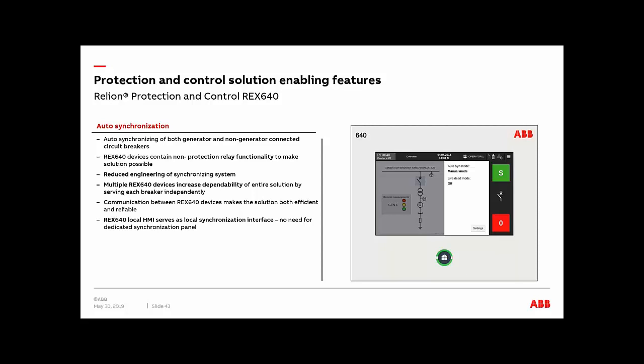And you can have multiple, actually in this scheme, you need to have multiple REX640. The system has to be comprised of 640 relays completely, so you can implement a successful auto-synchronizing scheme of, remember, up to 8 generators and 17 non-generator breakers. And as far as you having a dedicated panel for synchronization, each of the relays will have the information that you need with the synchroscope and all the information as far as the synchronization. So you can do it locally on the relay, or you could do it in the web browser as well, which will show you the same information you're looking at in the local HMI.